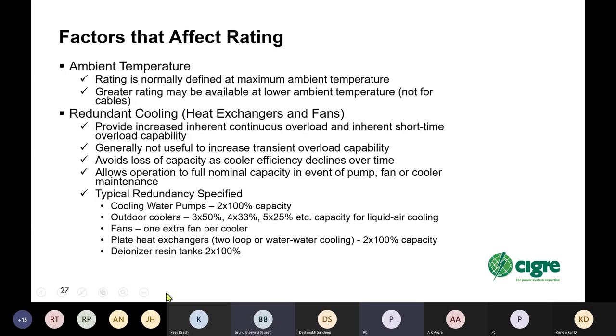So what are the factors that affect rating? Ambient temperature. Normally, you define the rating at maximum ambient temperature. You may get greater rating possibility at low ambient temperature, except if you have cables. Cables are underground, so the ambient temperature range is quite low, and typically you don't gain very much when the air ambient temperature changes in terms of rating. Another factor that can increase your rating is redundant cooling. And by redundant cooling, we mean extra heat exchangers and fans. They would provide increased inherent continuous overload and inherent short time overload capability. The extra cooling is generally not useful for increasing the transient overload capability.